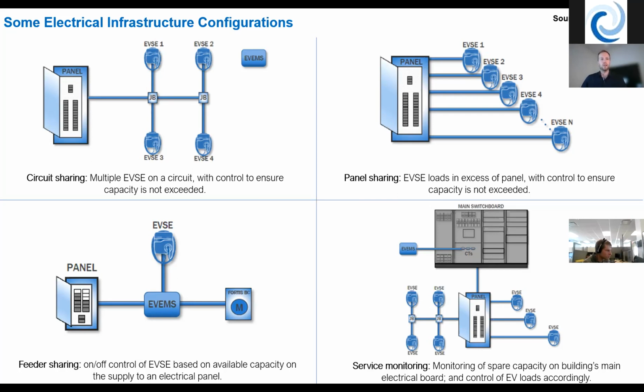And that's circuit sharing. So you're sharing multiple charging stations across a branch circuit coming off of this panel. There might be multiple branch circuits coming off of that panel, though it's not shown here, each supporting, in this case, 4 sharing that 40 amp circuit, and you can provide different levels of sharing. There's also panel sharing, which you see here in the top right, where you overload the capacity of the electrical panel. So if it's a 200 amp panel, you might have 400 amps worth of branch circuits off of that, but an EV energy management system controls it so that you don't exceed the capacity of that panel. There are systems like feeder sharing, where you're ensuring that, let's say, a home's electrical panel isn't being overloaded, and whenever there's capacity, providing that power to the EV charging station.